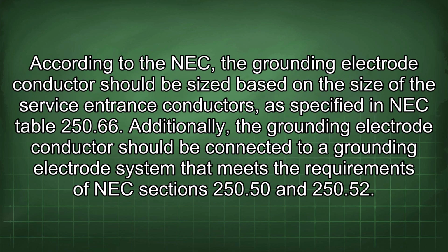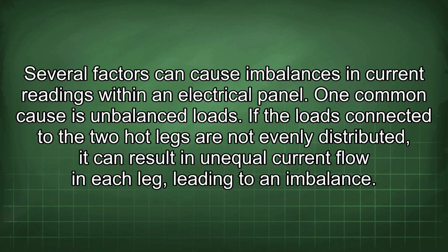According to the NEC, the grounding electrode conductor should be sized based on the size of the service entrance conductors, as specified in NEC Table 250.66. Additionally, the grounding electrode conductor should be connected to a grounding electrode system that meets the requirements of NEC Sections 250.50 and 250.52. Several factors can cause imbalances in current readings within an electrical panel.